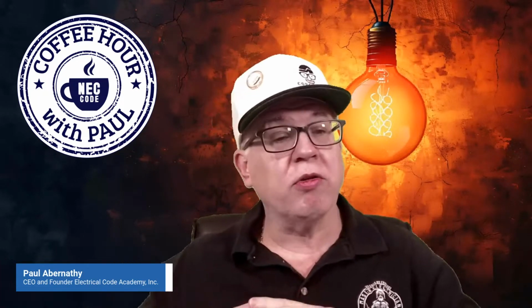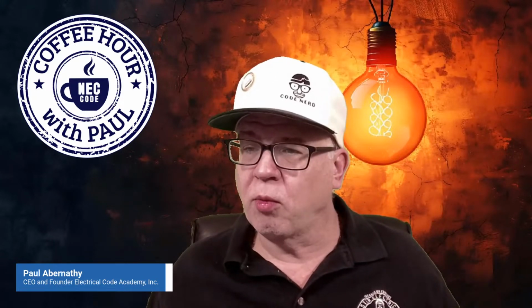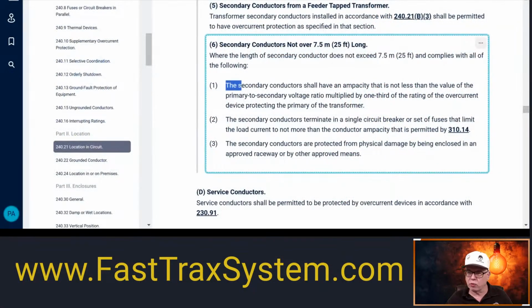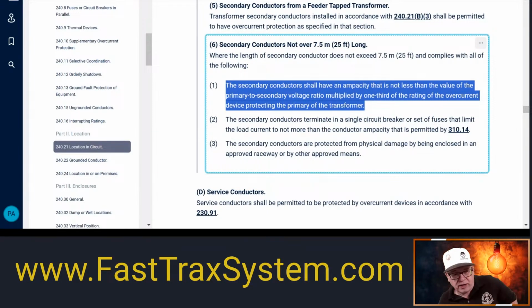Okay. So I still want to utilize this 25-foot rule. All that we saw with the rules here first was that we know the conductor itself, based on this rule, has to have at least 96 amps. Well, that's not going to be an issue for us. Now, that might be an exam question that asks you what the minimum size secondary conductor is for a transformer, and they give you the size of the transformer and the voltage and all this kind of stuff. But they might ask you what the minimum is. You've got to remember something. Just because a transformer can put out 200 amps doesn't mean I have to size it to 200 amps, right? A lot of people think that that's always the case. Well, I could have two separate 100 amps being supplied by this transformer. I could have two separate secondary conductor sets coming out, supplying two separate 100 amp panels, and still be well within the scope of that transformer.